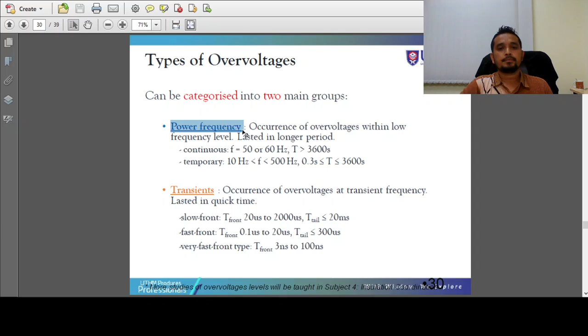Power frequency means 50 or 60 hertz. This is what we call low frequency voltage level, and in these circumstances the overvoltage will last longer. It happens in the range of 10 to 500 hertz, over a time period of 0.3 second up to 3600 seconds. That is power frequency, meaning the nominal frequency for standard electrical power systems, 50 and 60 hertz.